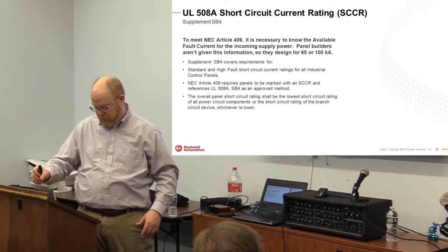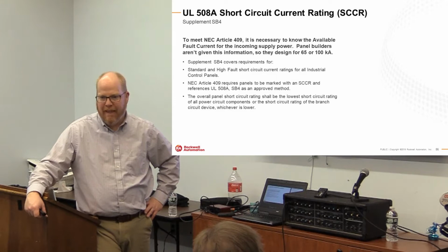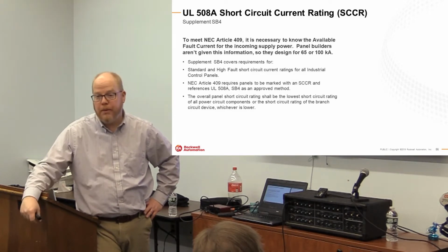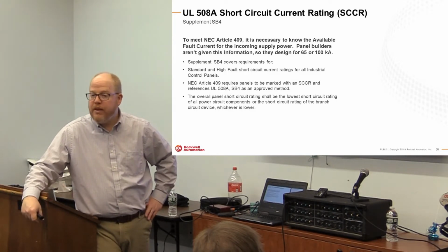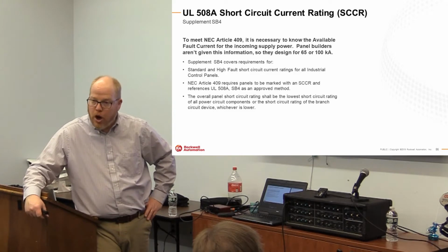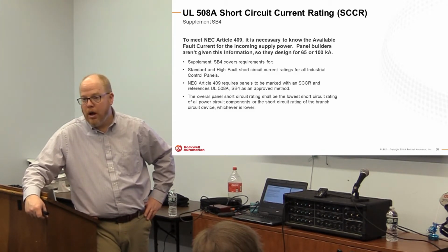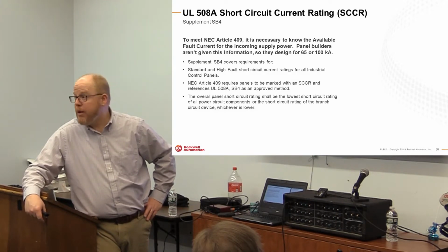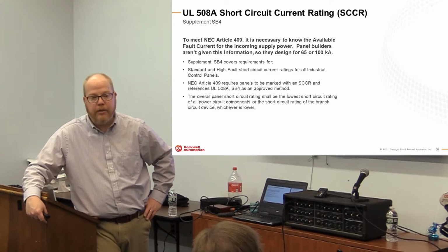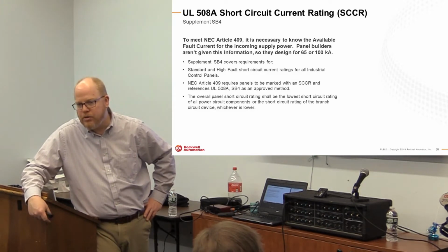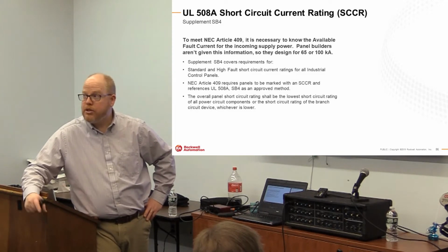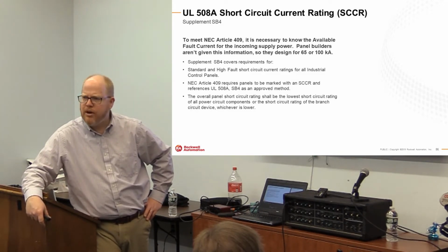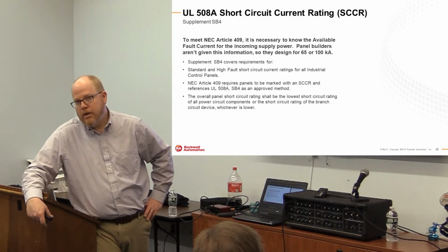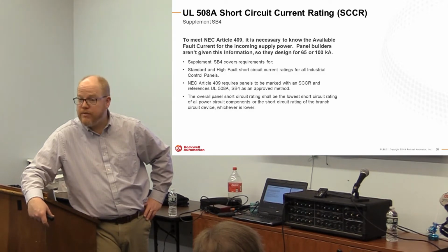But that's why I thought that the actual sticker has to be done by the end user, not by the panel builder. Now, this is a UL requirement. It's a 409 requirement. You have to put what the available fault could be. And it's up to them to install it to ensure that it's not subject to a short available fault current greater than that. So I have many of my customers that don't want to go through all this mess, and they'll put 5 kA on the label. And then they put the onus on the customer to not install it above 5 kA. Now, is that a commercially viable solution? Maybe, maybe not. Some customers say, well, I'm going to pick 65, because that's a very high threshold. And it's up to them to not install it at something greater than 65. The onus of the installation is still on the user. I don't know if that clears things up for you.